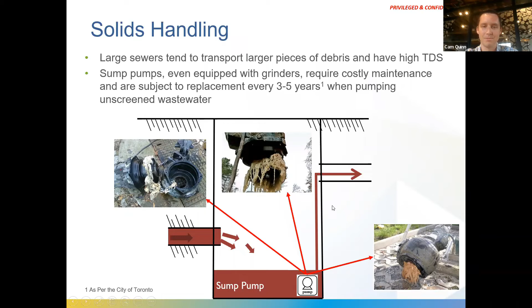So that's more on the screening side. If you're able to get the wastewater through the pump to the heat exchanger, we come up with 2 additional challenges. The first one is biofouling, and this is probably the greatest challenge for wastewater systems.